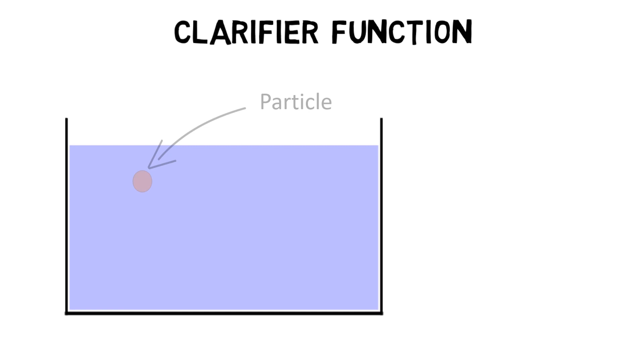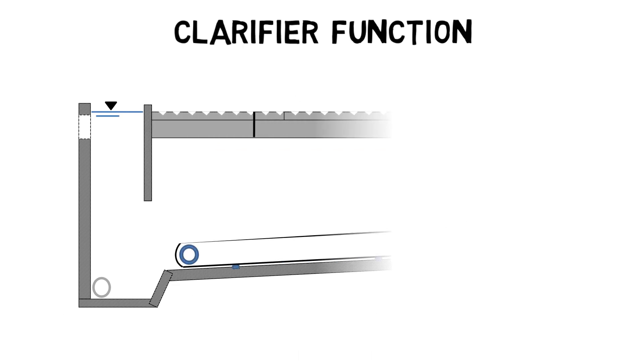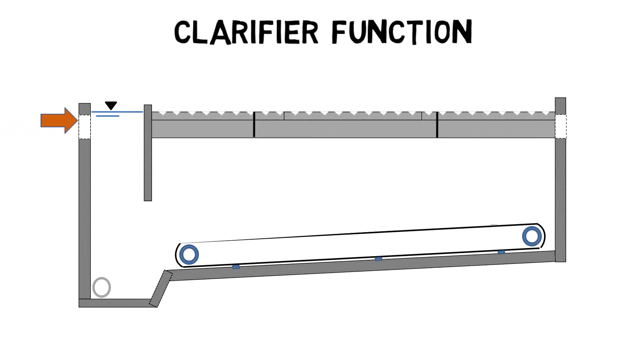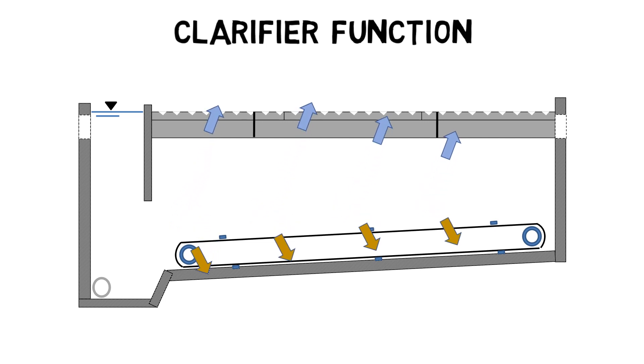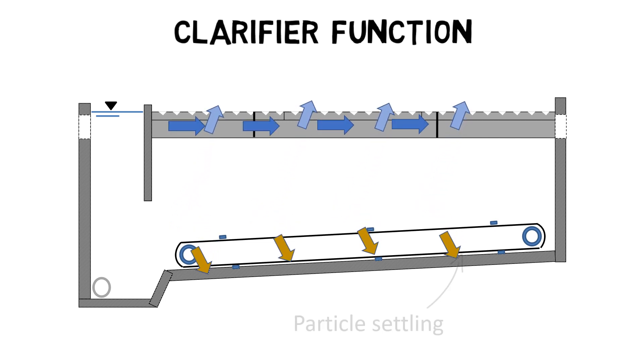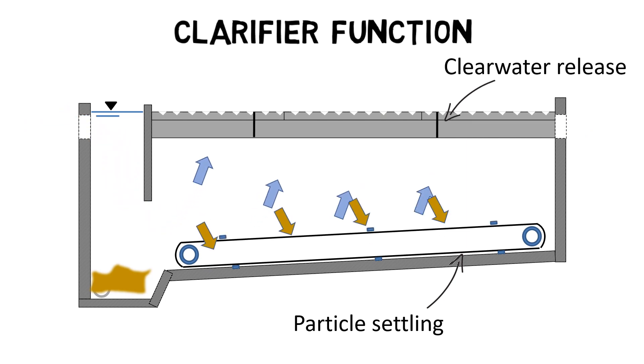Settling is the tendency for particles to fall through the liquid in which they are entrained. The same principle is used by wastewater treatment plants to separate particles from wastewater. In clarifiers, particles settle down as sludge to the basin bottom and the clearer water is released over effluent launders on top of the basin.